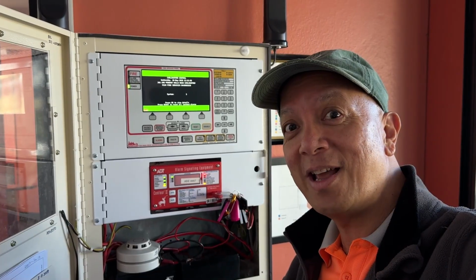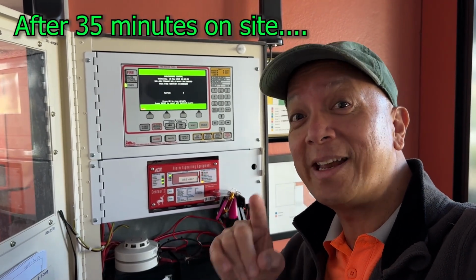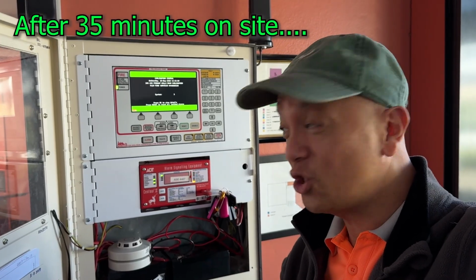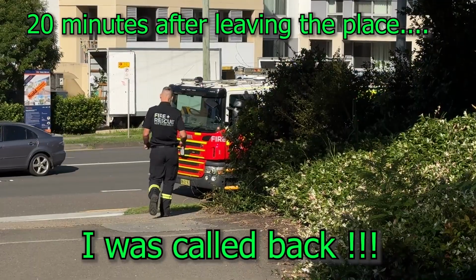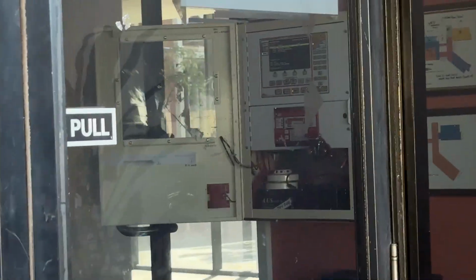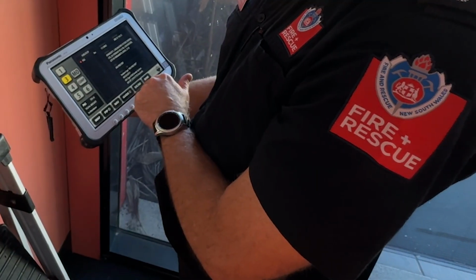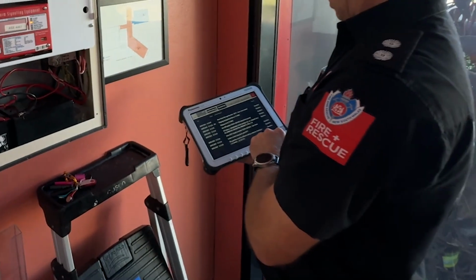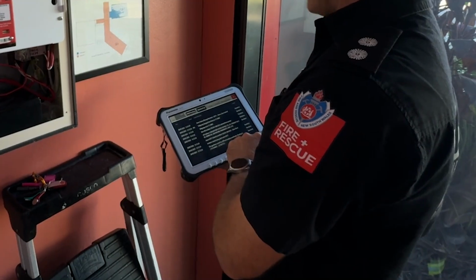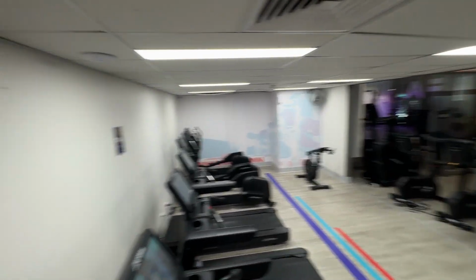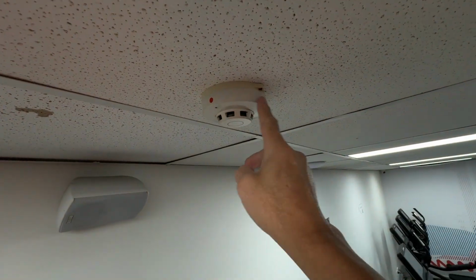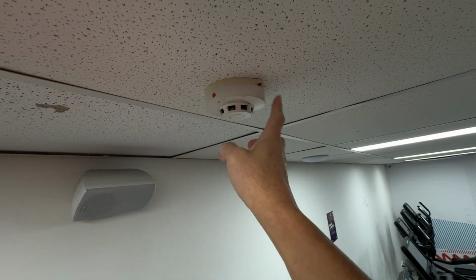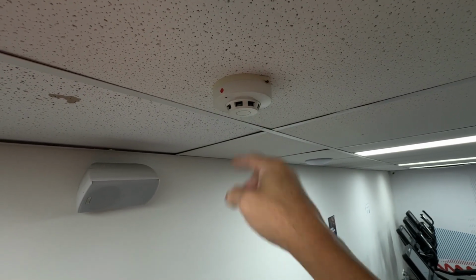Okay, so let's go to the fire panel and isolate or enable everything. Been a while. I did not remove my ASE while I was on site. So I've finished. I'm going to remove the ASE and leave the place. This is what I don't want you to experience. After 30 minutes, when I left the site, the alarm went off again and the fire brigade attended. Lucky I met the fire brigade guys here and they showed me where the alarm is coming from. Okay, it's inside Fitness First. There's another alarm, possibly a dirty detector. This time they found the alarm.